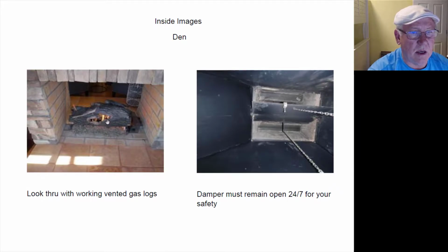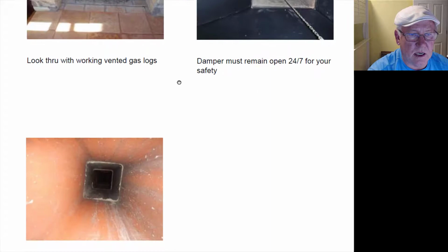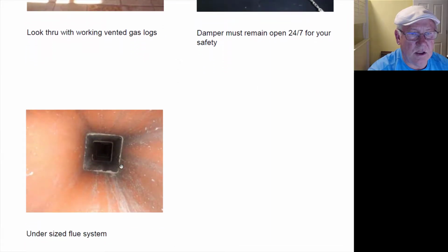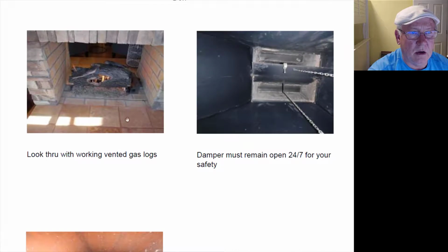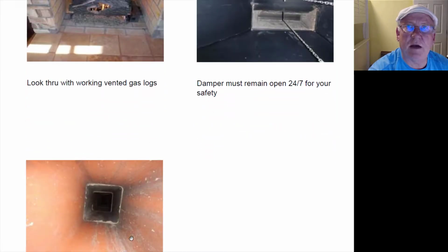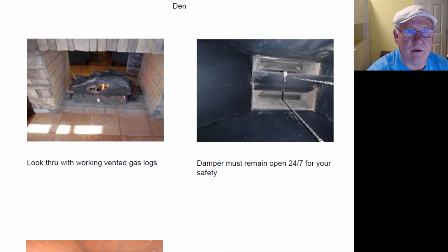So anyway, on this fireplace, the flue size is 13 by 13, and it should be, because you have an opening of 42 by 30, which is very large, an oversized opening on both sides. You're pulling air in from both sides. It's not all going to go sailing up this chimney because a 13 by 13 flue, which is what you have, and I don't want to bog you down in a bunch of information and confuse you, but the bottom line is this size flue that you have in your chimney was designed for a one-sided fireplace with a standard opening, which is 36 by 30. This is a 42 by 30 on both sides.